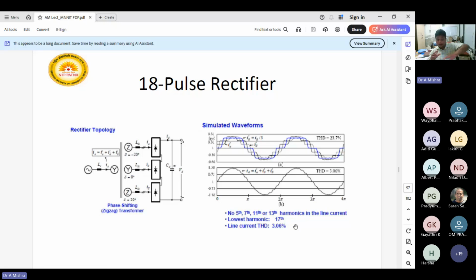This line current, remember again, I am talking about the input current. The input power factor part I have discussed, how it is disturbing the power factor. Similarly, I am not drawing a sine wave current. I am drawing non-sinusoidal current, which means I am injecting harmonics into the system. If I am injecting harmonics at a higher level, it should be a punishable offense. Actually, if it is not, it should be. Because if you are using some equipment that is disturbing the power supply system, that is not good for others. So higher pulse number converters inject fewer harmonics, not into the transmission but to the transformer, and you are spreading them in the whole system. So a higher pulse number reduces the total harmonic distortion.